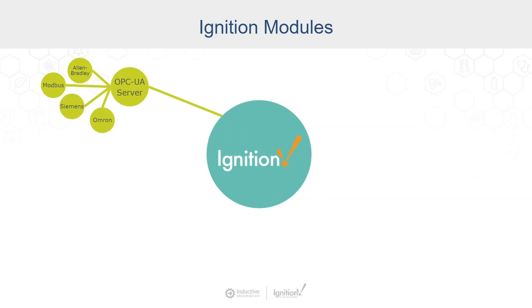We built an OPC UA server in Ignition so that other applications can connect to us as a client. Ignition can handle that, and a lot of people use it just as an OPC server. But if you want to go further, you can start adding more modules and functionality. For example, we have a SQL Bridge module that provides transaction groups — it's a Swiss Army knife where we can move data between PLCs and databases, do contextual event logging, basic history, recipe control, or synchronizing values. You can add the historian to have a process historian that logs to any SQL database.